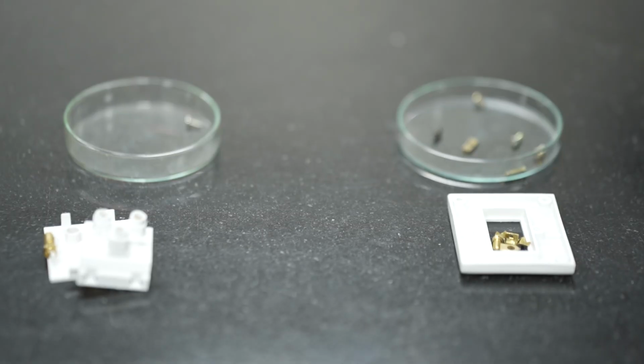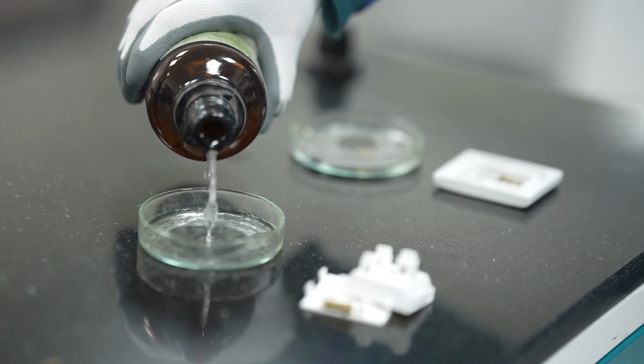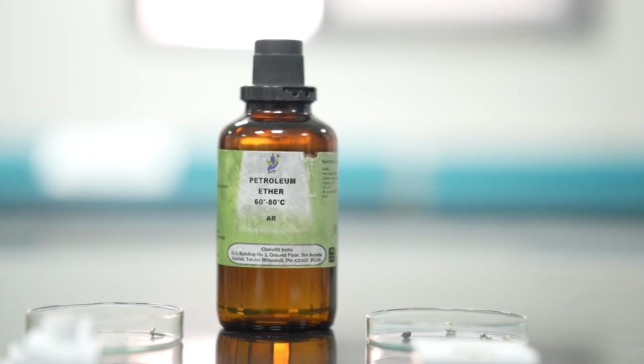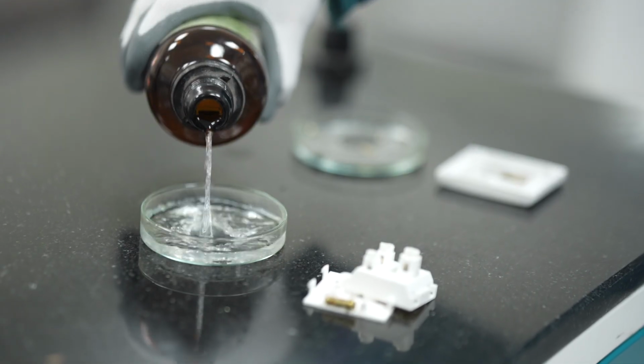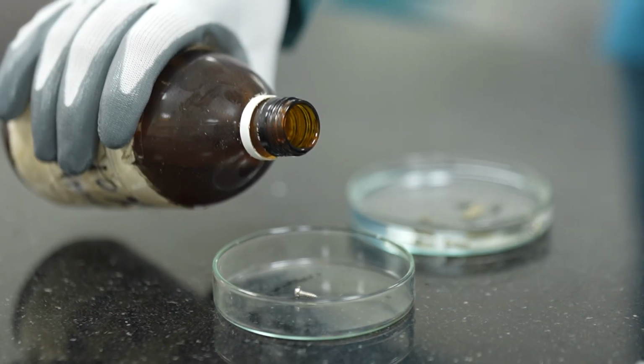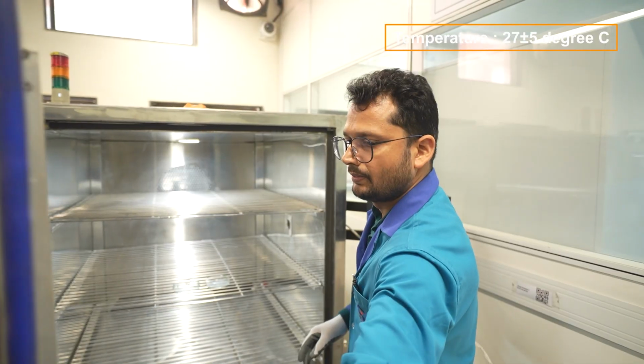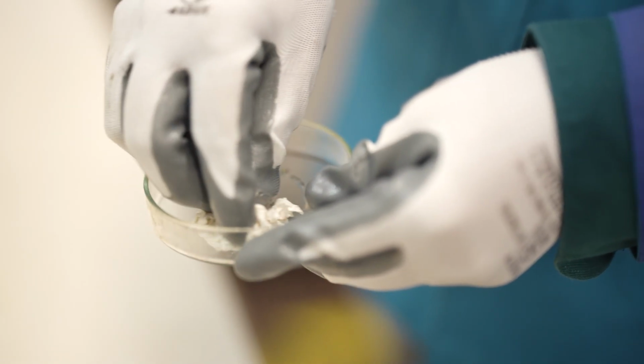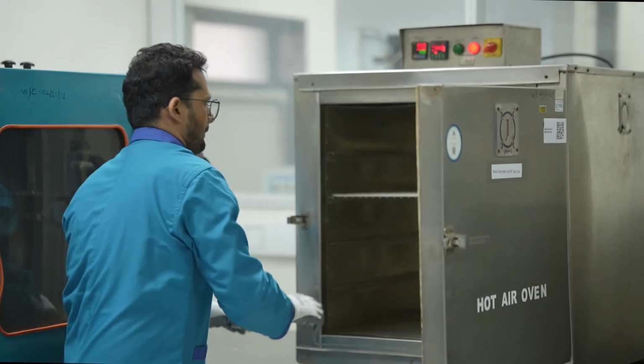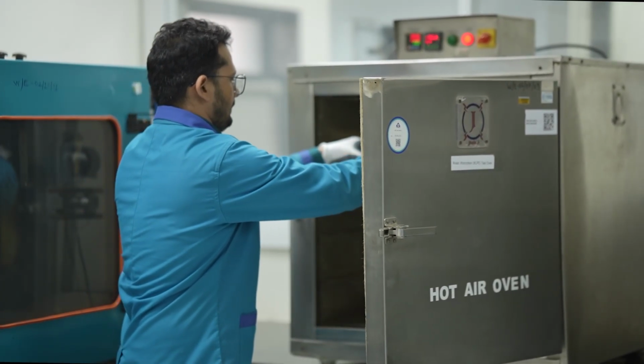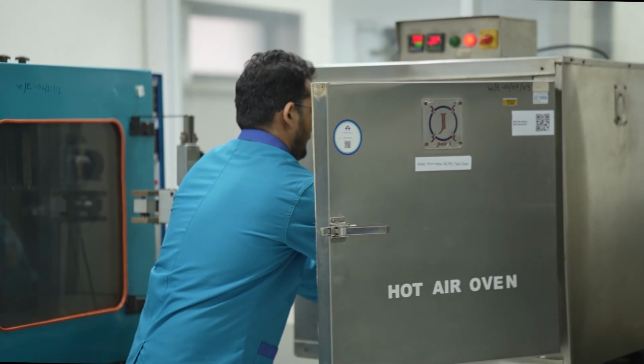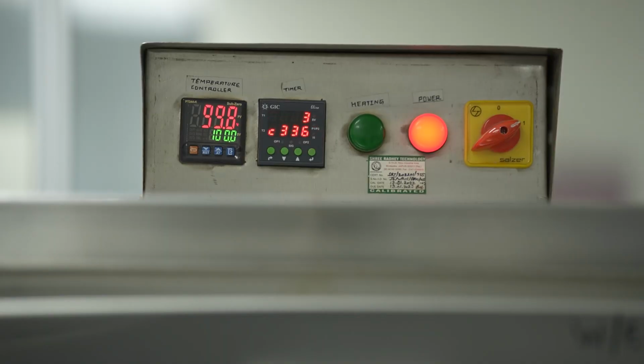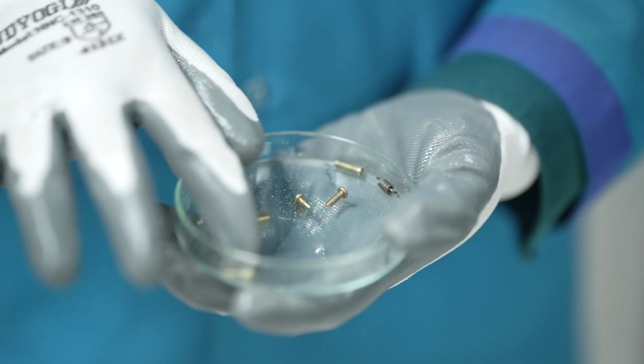Resistance to rusting. Clause 29. Ferrous parts including covers and surface mounting boxes shall be adequately protected against rust. All grease is removed by immersing the test parts in a degreasing agent for 10 minutes. The parts are then submerged in a 10% ammonium chloride solution at 27 ± 5 degrees Celsius for 10 minutes. Without drying, but after shaking off excess liquid, the parts are placed in a moisture saturated air chamber at 27 ± 5 degrees Celsius for 10 minutes. Finally, the parts are dried in a heating cabinet at 100 ± 5 degrees Celsius for 10 minutes. These surfaces must show no sign of rust.